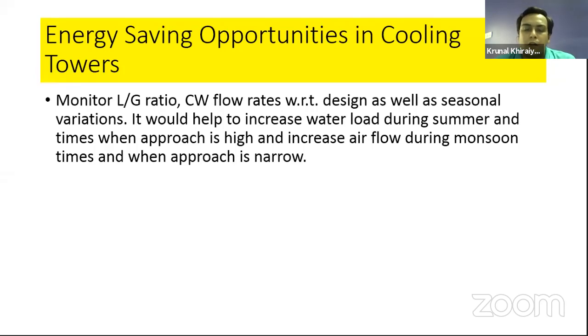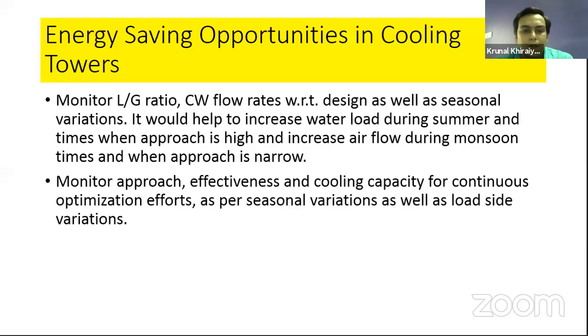Suppose whatever cooling tower you purchase from the manufacturer is supplied with some standard design parameters. You need to check whether the L/G ratio is near the rated one or not. And seasonally it varies, so according to your catalog or the operating process suggested by the manufacturer, you need to make some variations in your operating conditions. Monitor approach, effectiveness and cooling capacity for continuous optimization efforts as per seasonal variations and load variations.